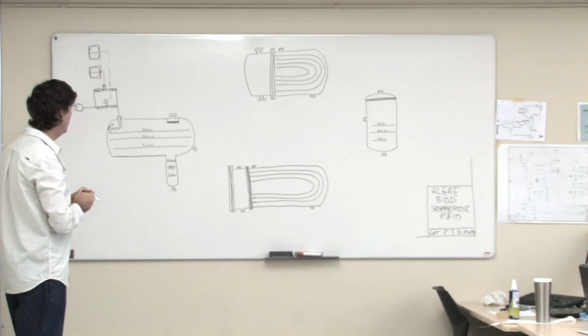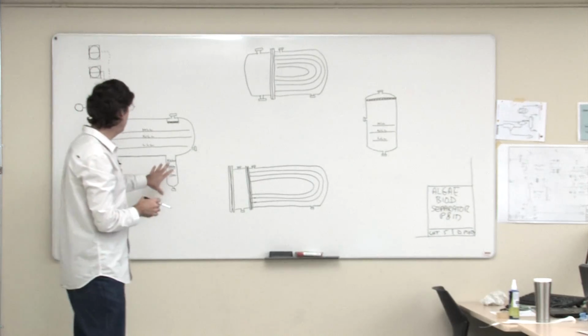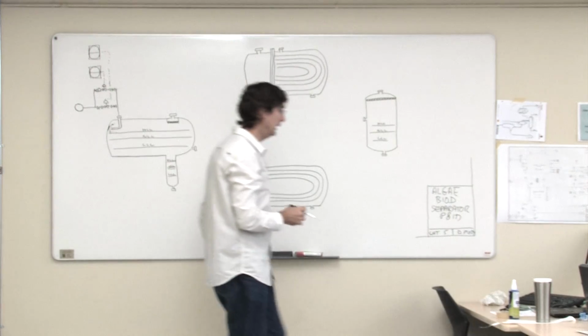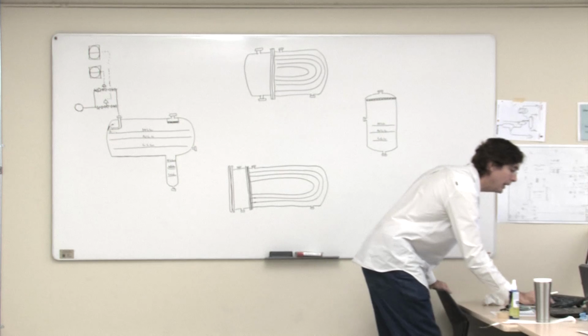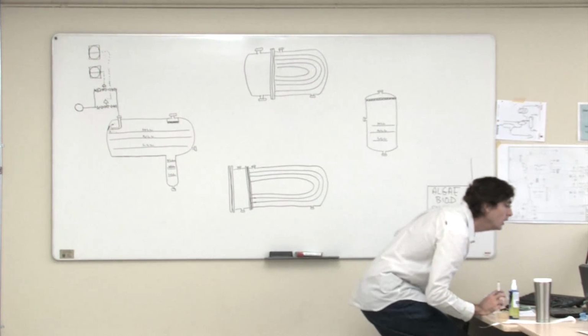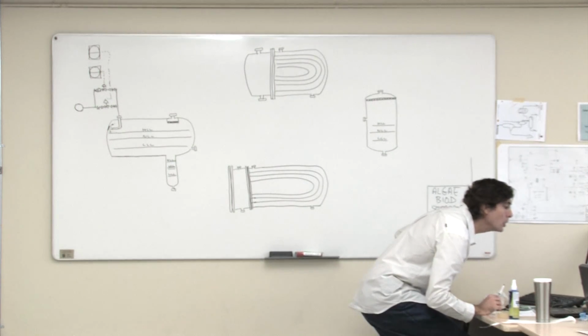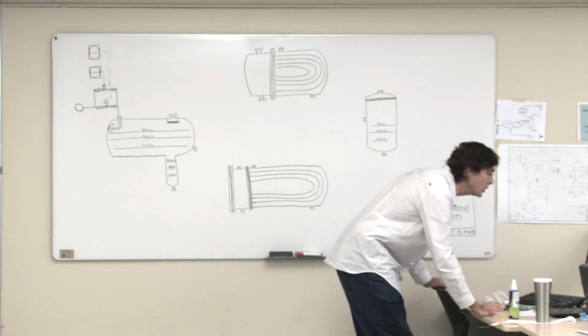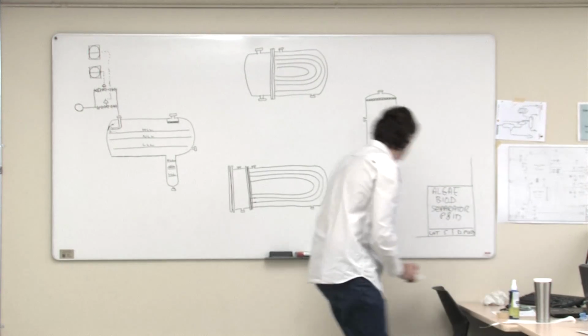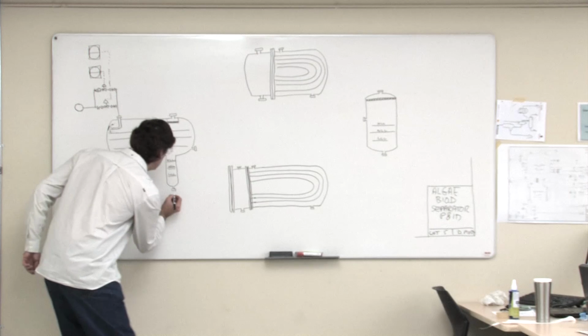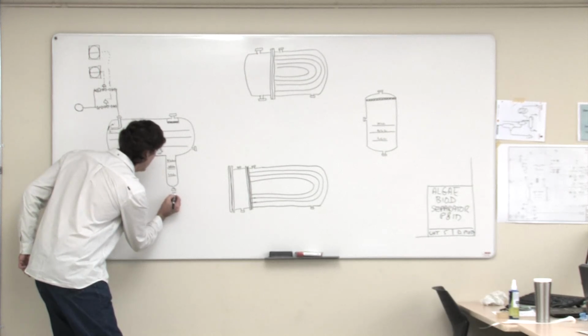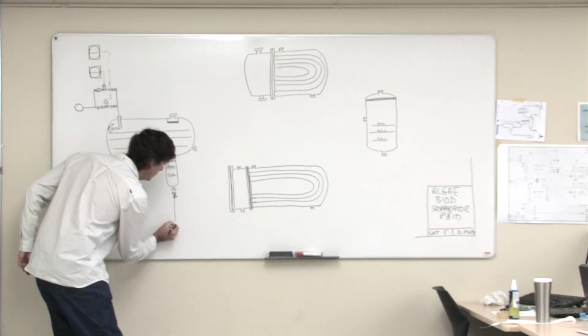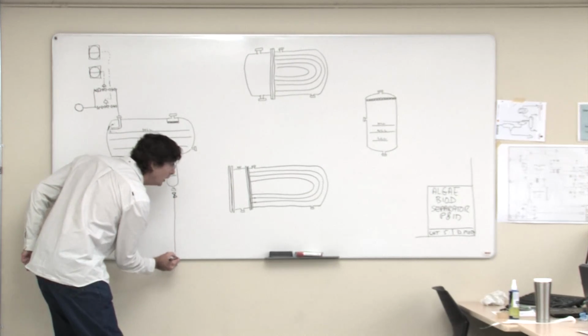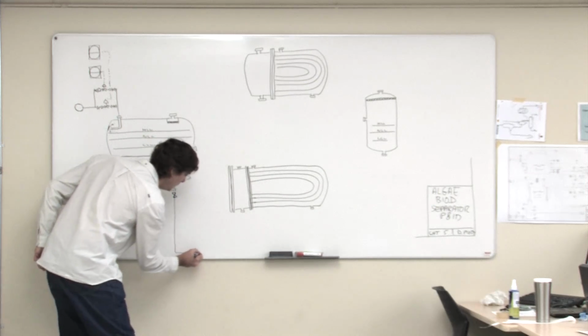Okay, the easy one is the water, because it just goes right off the P&ID, right? Yeah, it goes on to sheet 3 where there's some cross exchangers and stuff like that. So we don't have to worry about it on this P&ID. We probably want to have a manual isolation valve on the piping, so not a control valve, just a valve to isolate it, since I'm not going anywhere with it.